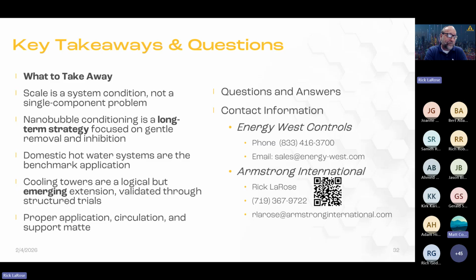Another question: can you use this on a condensate return line? We get asked that a lot, so here's where we're at. Remember the conditions that have to exist for this to work: we need fresh water constantly coming in with non-condensable gas, and we need a place for that gas to go later. Typically in a condensate system you don't have that, especially since you're deaerating, trying to get the air out of the condensate.